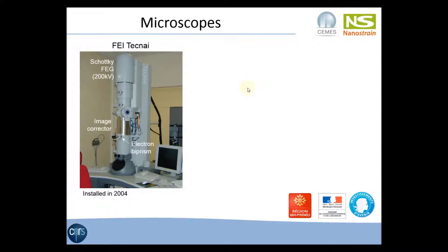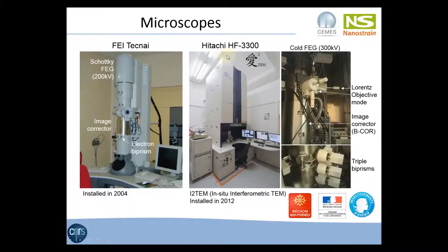To do this, we use two microscopes. The first one is a FEI Tecnai machine with a Schottky field emission gun, an image corrector, and a single electron biprism. For this presentation, holography was carried out using the Lorentz stage, which is above the objective lens, in order to have a large field of view, and using two biprisms in order to remove the Fresnel fringes and have better control of the hologram width and the fringe spacing.